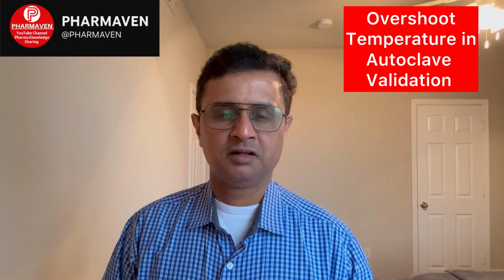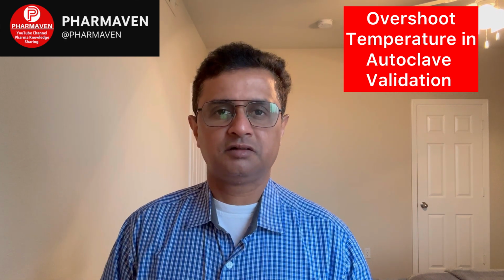The third point is to check the load arrangement. Was there any change in the load arrangement? Was it the same as the previous validation, the same as what we put in routine, or is there any change, an increase or decrease in numbers or placement? Have we changed the placement of the load components? We can see this and identify if there is a change in the load. Fourth is sensor placement. Was the sensor placement accurate, was it as per the protocol? Were there any changes? Was it touching the metal surfaces or any other component?